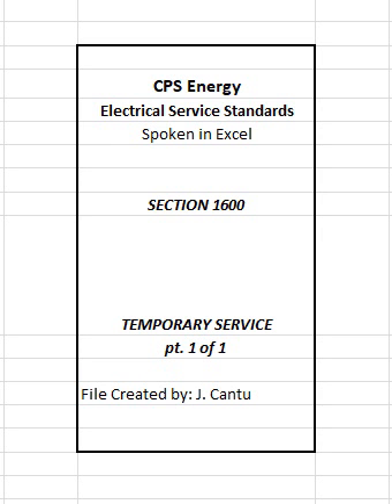1. Customer shall provide a minimum of 24 inches of free conductor for connection to service drop by CPS Energy. 2. Conductors shall be installed in approved raceways of RMC, IMC, or EMT. Service raceway shall be a minimum of 1 1/4 inches and be securely supported to customer's temporary meter structure. 3. Drip loop conductors and service drop conductors shall be installed so as to maintain the minimum vertical clearance requirements outlined in Section 500 and shown in Figure 501.